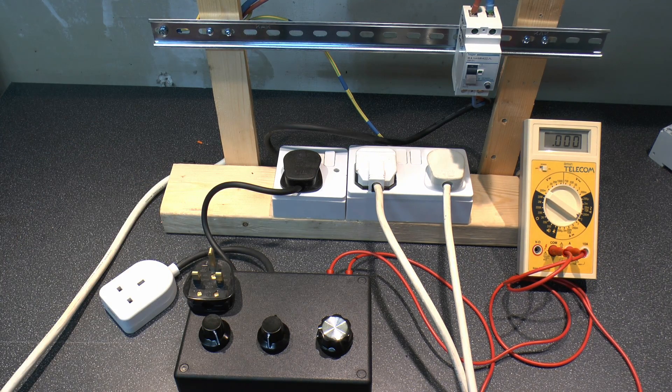So the prevalence of semiconductors, and more specifically diodes and rectifiers, they're in pretty much everything these days. So this type of fault, where you've got either pulse DC you've got from this single diode, or even just smooth DC going through the RCD, is something which is going to be fairly likely, and in some cases almost inevitable, having the huge prevalence of electronic equipment these days.